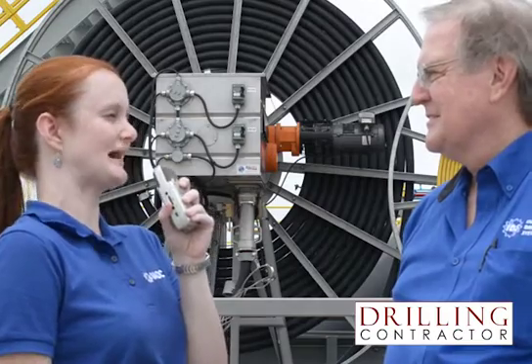How is this system unique compared to traditional power delivery systems? Traditionally, the generators generate 600 volts, and all of the motor control equipment is in one large electrical building that stays in one place near the generators, and then 600 volts is distributed throughout the drilling rig. But each motor has to have cables run from the main powerhouse out to the motor. This system starts with 600 volts and then steps up the voltage to 4,000 volts and then distributes it to the movable part of the drilling rig. In order to do this, we had to distribute the electronic equipment throughout the rig — so instead of one big electrical house, we now have the electrical equipment in the driller's cabin and in other places, and we just distribute power to it with no control wires.